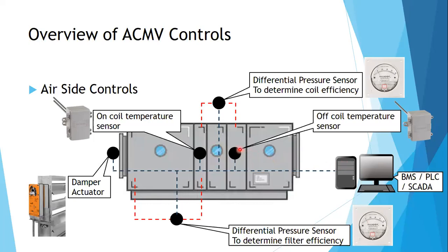Another field device within the AHU is your on-coil and off-coil temperature sensor. This on-coil and off-coil temperature sensor will tell you what is the heat load being transferred to the room or from the room. So you will be able to know what is the cooling capacity, what is the cooling requirement of your area. So this on-coil and off-coil temperature sensor will verify your cooling capacity, or the performance of your air handling unit.